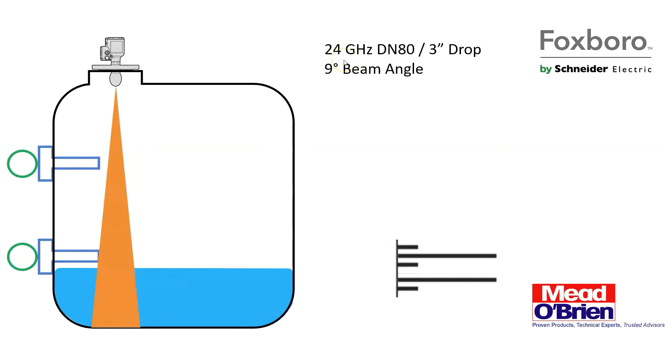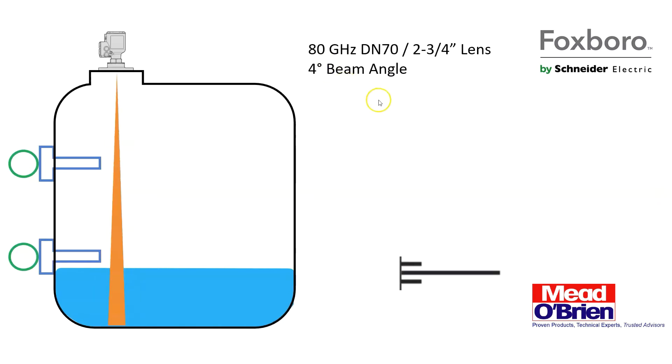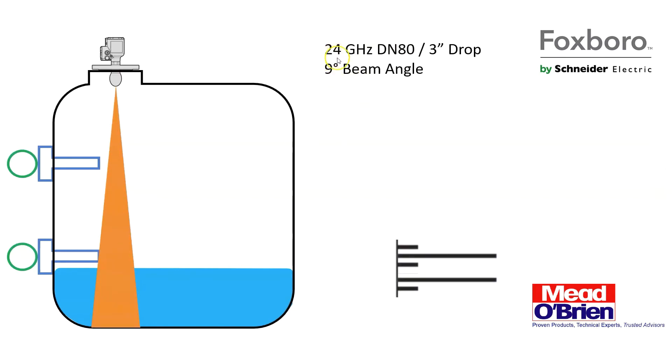So when you get to a 24 gigahertz, we notice that the beam gets a little smaller. Remember, the lower the frequency, the wider the beam. So as we get to a much higher frequency, we're going to see a smaller beam. But here at 24, we're kind of in the middle. So we've got a three-inch drop antenna on this one, a nine-degree beam angle, and the same size tank, same dimensions.